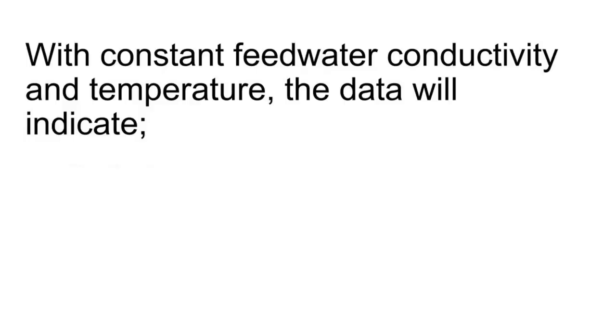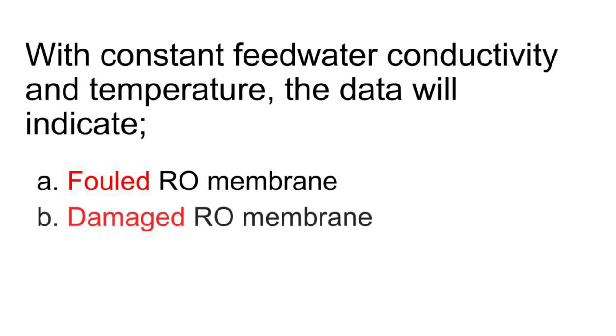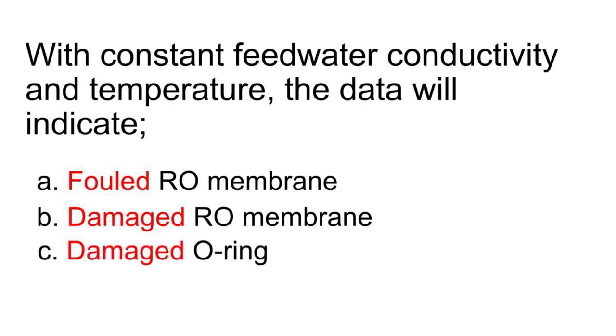If the feed water temperature and conductivity are constant, the data tells you the following. A higher feed water pressure indicates RO membrane fouling. A combination of lower feed water pressure and higher product conductivity indicates RO membrane damage. If the feed water pressure is relatively unchanged and the product conductivity is higher, internal O-rings are probably damaged.